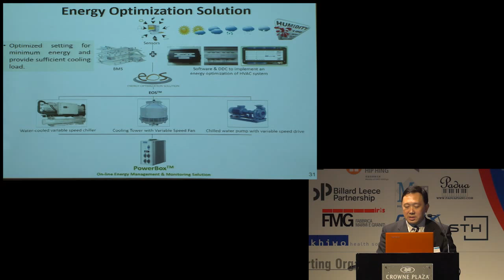Now, with this system, I'll give one example. We've been doing a lot of simulations, and we estimate that it's quite possible that we save around 17% of the annual air conditioning energy. Now, how can we do that? Because a lot of time, people will think, turn the chiller to the maximum capacity to produce a cooling load. But very often, the chiller is the highest consumption of energy. If somehow you turn the cooling tower a bit higher, the pump speed a bit higher, but lower the chiller energy, then actually you can optimize the system.